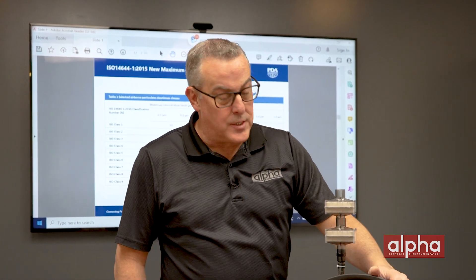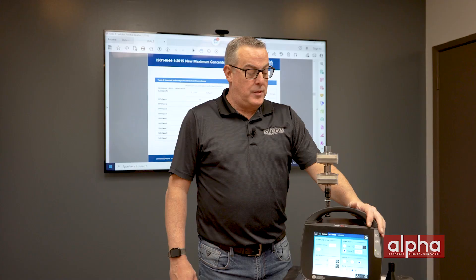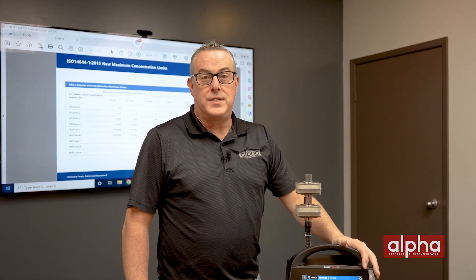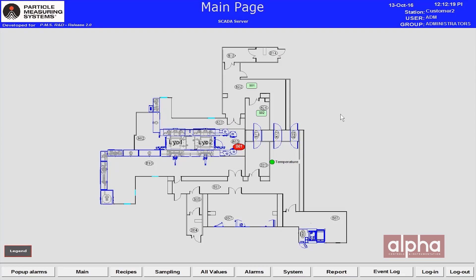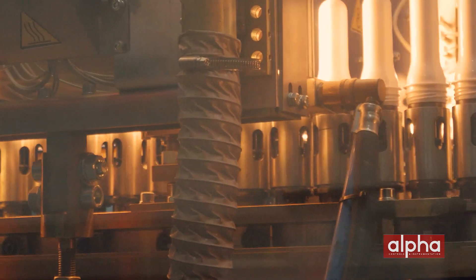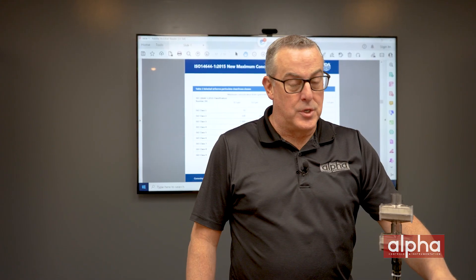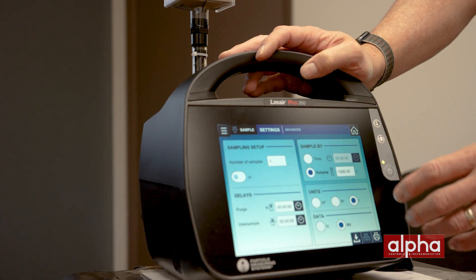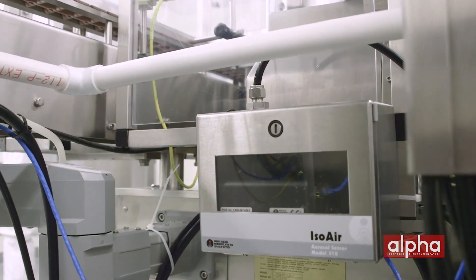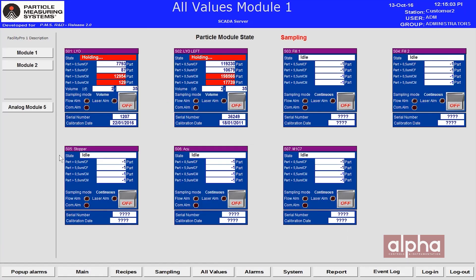We've been selling and servicing particle measuring systems equipment for over 8 years. Today we're going to talk about the new Lasair Pro particle counter. This particle counter comes in three different flow rates: 1 CFM, 50, and 100 liters per minute. The 1 CFM and 50 liter per minute is typically used for continuous monitoring in ISO 5 areas, where the 100 liter per minute is typically used in less frequently monitored areas like ISO 7 and ISO 8, and is the most common flow rate used for compressed gas monitoring. To run a sample, you simply program the sample recipe and hit start. The sample is then drawn through the machine and passed through a laser which detects the amount of light scattering of the particle. This light scattering is what determines the size of the particle.